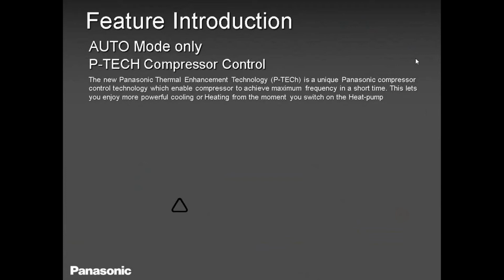Auto mode. Everybody likes auto mode, but I'm not a big fan of it, because 2 hours it's doing cooling, another 2 hours it's doing heating. You're fighting against each other all the time in the room. In my case, I like auto mode probably in the fall or springtime, where in the morning it's cold and then in the evening or afternoon it's hot. That's the only time I will use auto mode. But come October onwards, I will always use heat mode, or in summer, I will always use cool mode. I don't want to waste energy. And in a shoulder season, why not use fresh air? Just shut off the unit, open up the windows, and get some fresh air. But some guys like to use auto mode. It's there, you can use it, no problem.